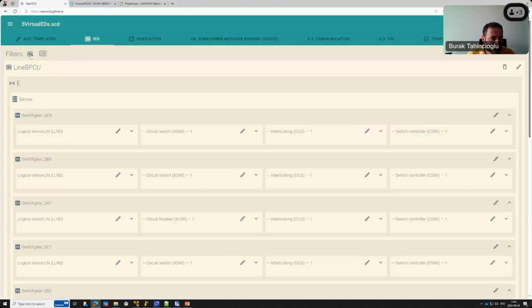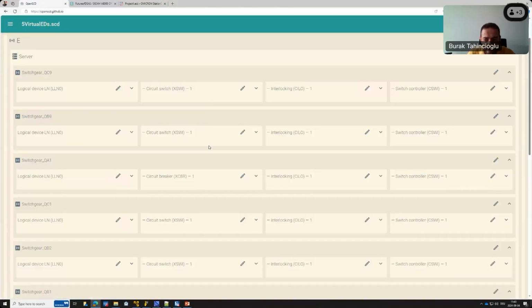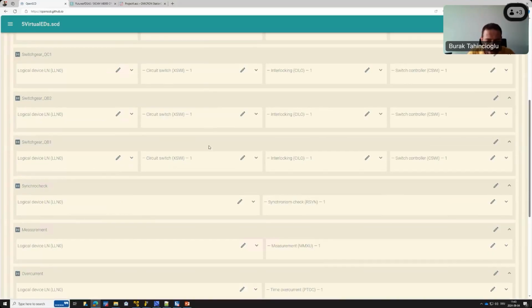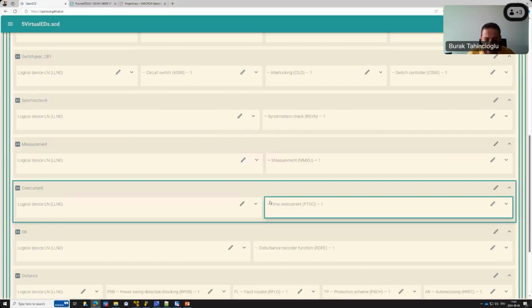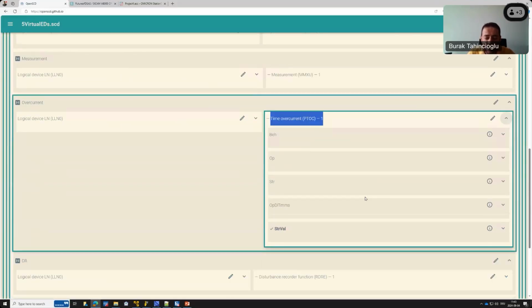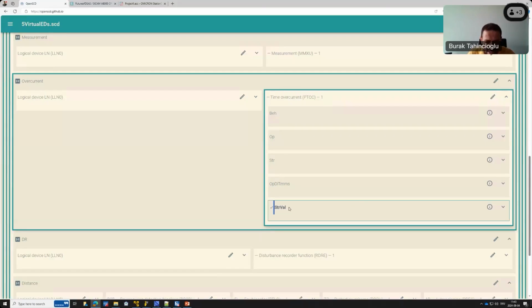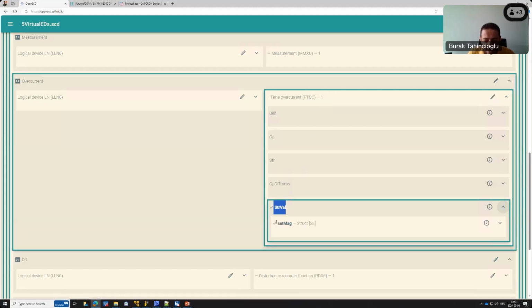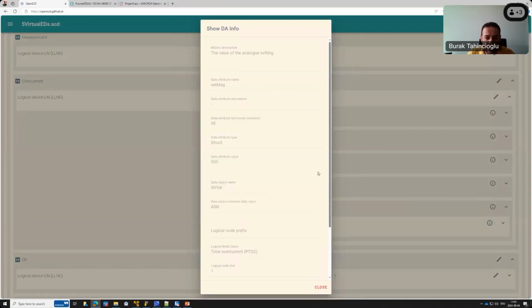I select from here, and then I need to find my logical node, which has the time over current setting under that. So having the setting in the 61850 data model is again not mandatory. You can optionally have it, and if you have it, here is the start value of this PTOC, the first stage of it. And if you have it, you can also have the setting of it, and you can even set the value for that.